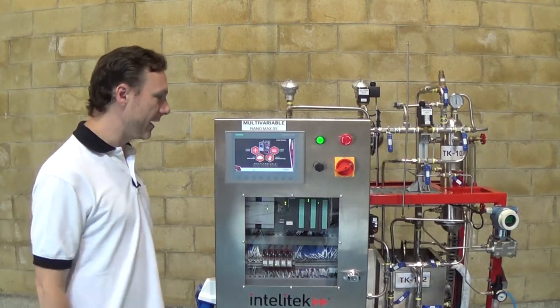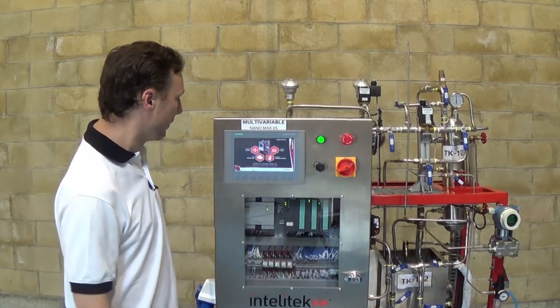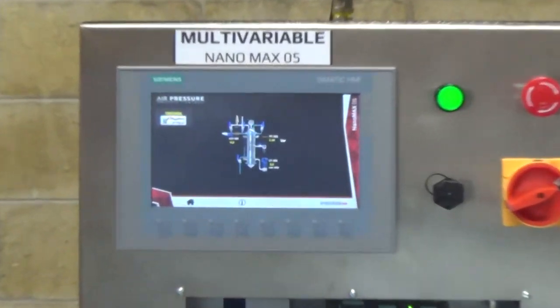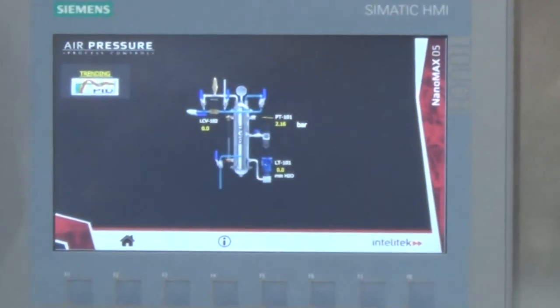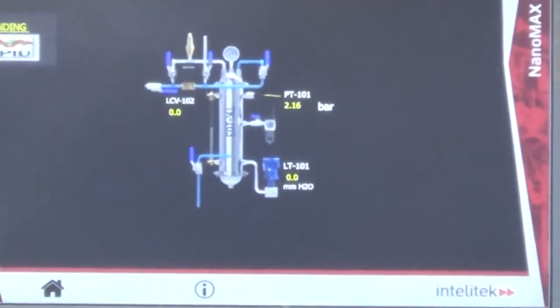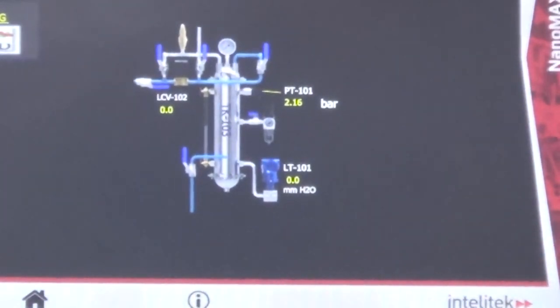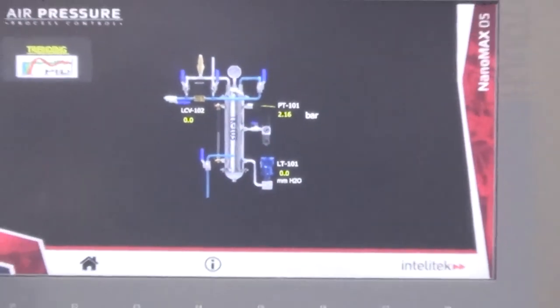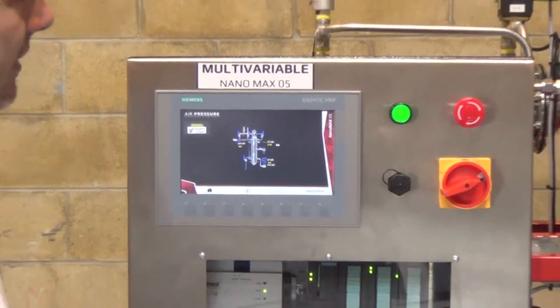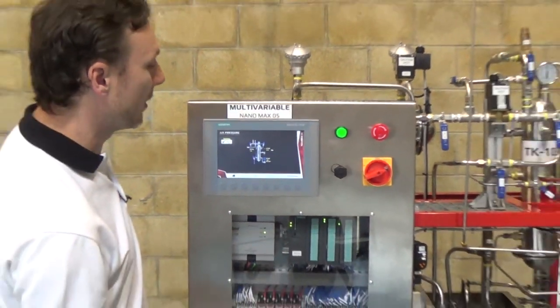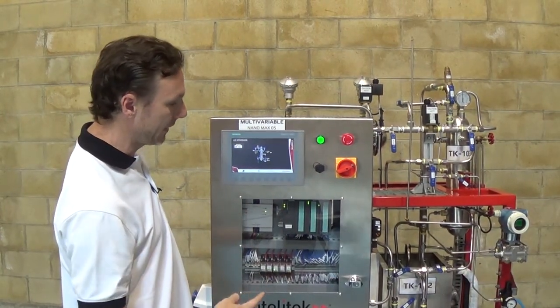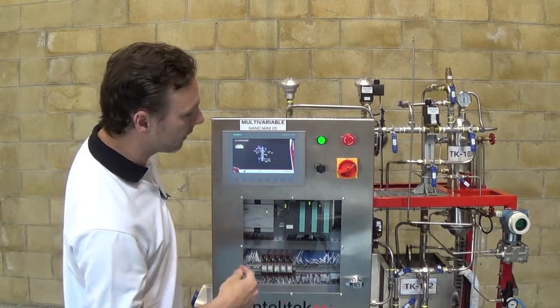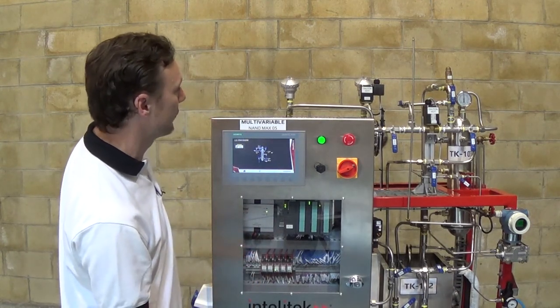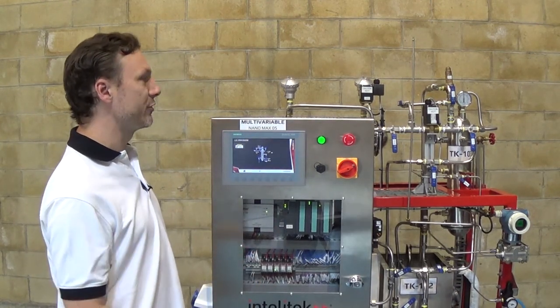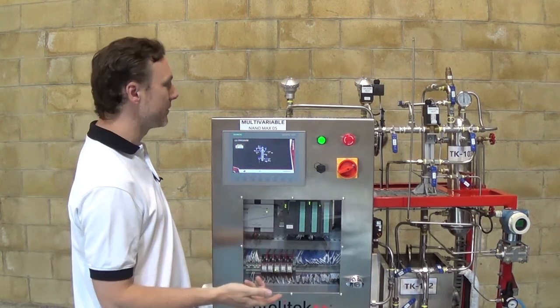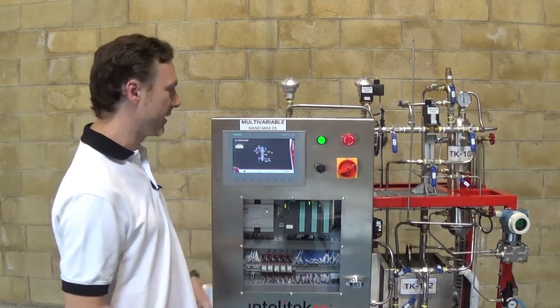Okay, next we'll take a look at air pressure process. So I'm going to click air pressure or touch it. Again, we're showing what we're actively working on, and we're basically looking at the air pressure tank. There's an air pressure gauge at the top of the tank, and what we're doing is we're feeding in air, and we're trying to maintain a certain set point of air pressure inside the tank, despite disturbances that are created by outside sources.